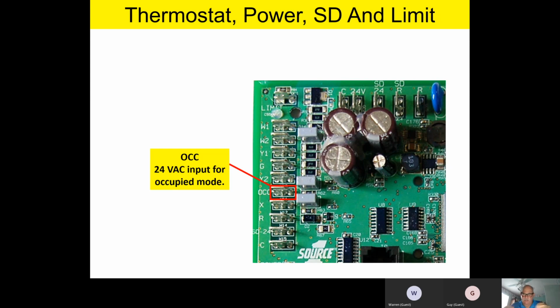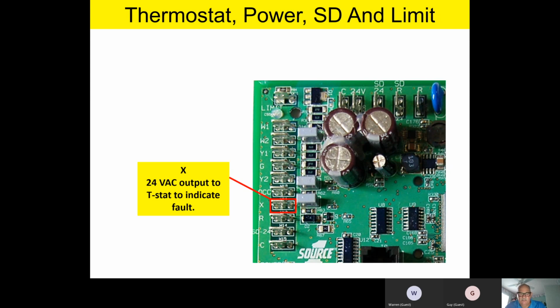Okay, so fellas, as we move down the board on the thermostat side, there's an X terminal. That X terminal is an output from the board to the thermostat to indicate a fault. So if you've got a fault on the board, it'll output a 24-volt signal. It'll just click a relay. It'll output a 24-volt signal on that X terminal to alert that there's a problem on the board. Now, it should be noted that this is only going to work if your thermostat is equipped with a fault light. So if you've got a 24-volt thermostat that has a fault light, you can hook that X wire to it, and it'll just flash that fault light if you've got a fault on the board. So it's strictly an output from the board, and has nothing to do with the function of the board. It's a fault reporting circuit.